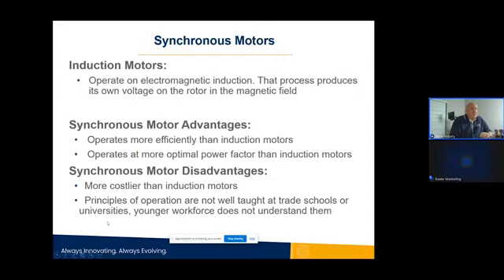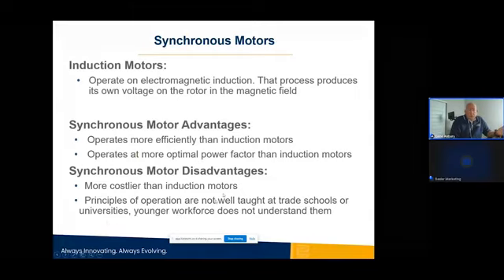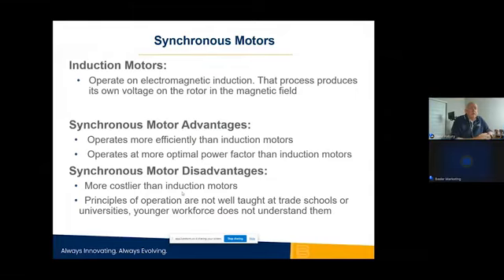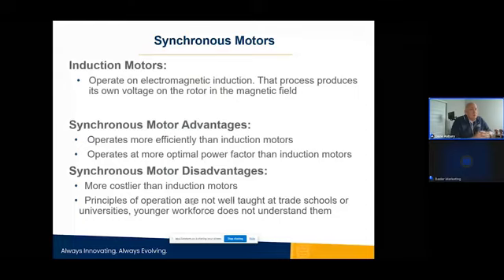Some of the disadvantages of synchronous motors: they're more costly because now you've got a field winding that you don't have in an induction motor, plus you have the controls to control that field winding, to regulate the power factor, and all the other components needed to apply the field at the correct time. Also, the principle of operation of a synchronous motor isn't taught at many schools, so the workforce is not as familiar with synchronous motors as probably they should be.